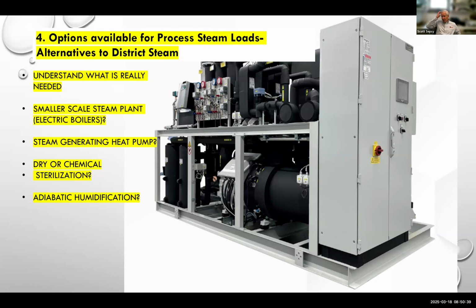Steam generation could be done instead of a district system. It could be integral to the equipment. You could have local generation for multiple devices in adjacent buildings. Building power has to be studied, though, if you try to electrify the process. If you have a satellite plant for just a cluster of buildings compared to district heating, the demand might get too large and you may require a boiler operator.